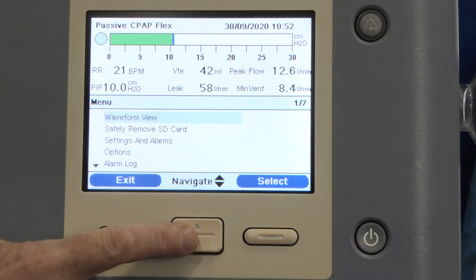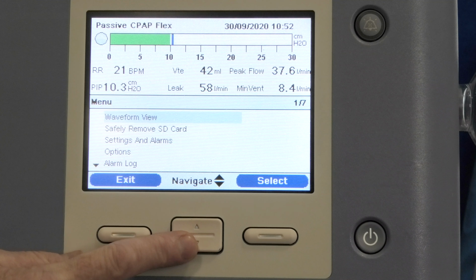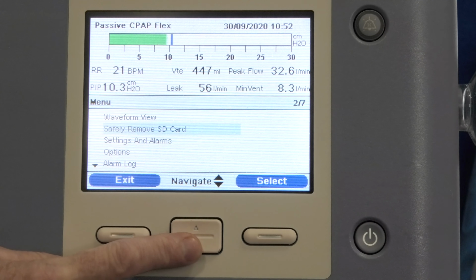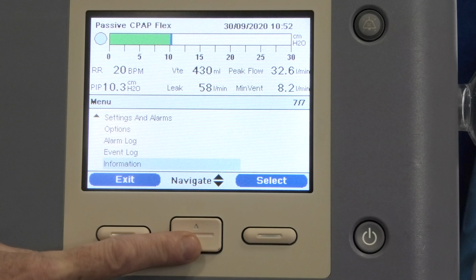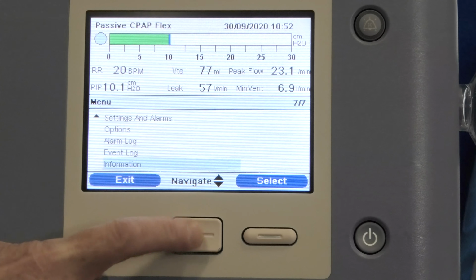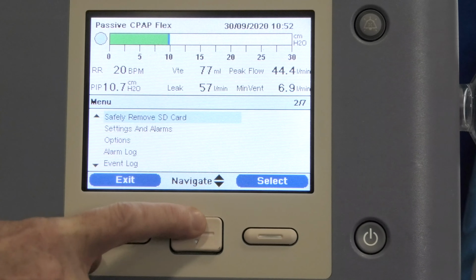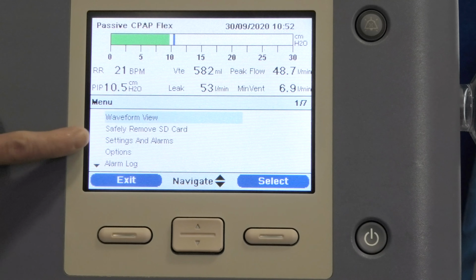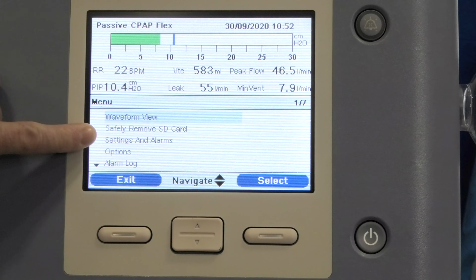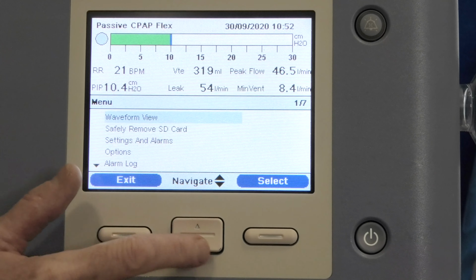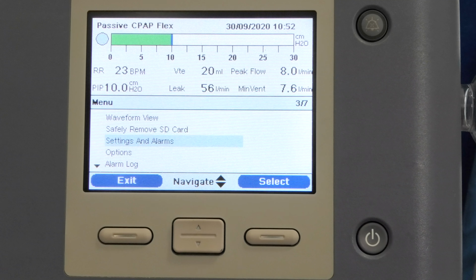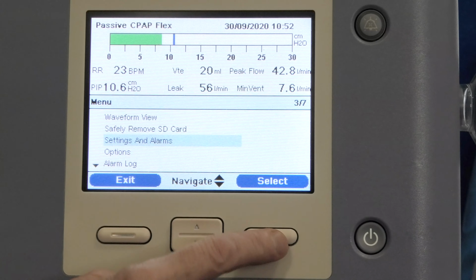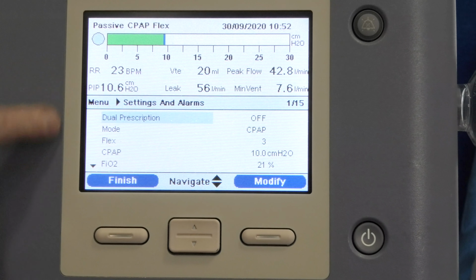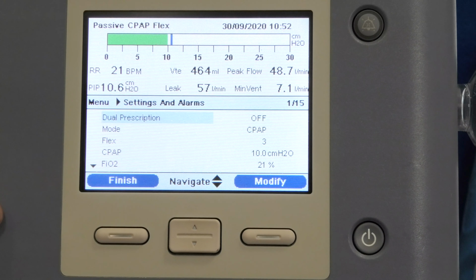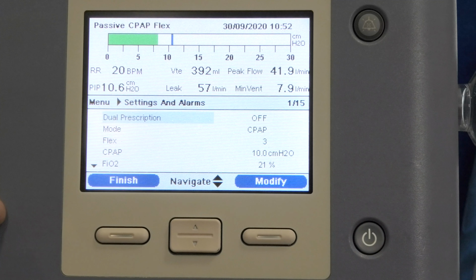We have a variety of things in here, such as waveform view, safely remove your SD card, and so on. So if we scroll down, we've got event logs and alarm logs. So we can navigate between those with the navigation keys. Everything that you would want to change is in settings and alarms. So if you scroll down to settings and alarms and press select, it will take you into the CPAP settings that our patient is receiving at the moment.